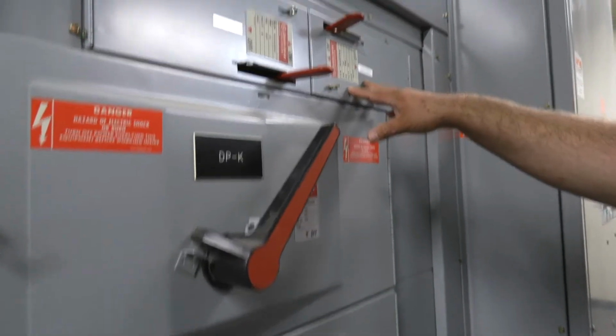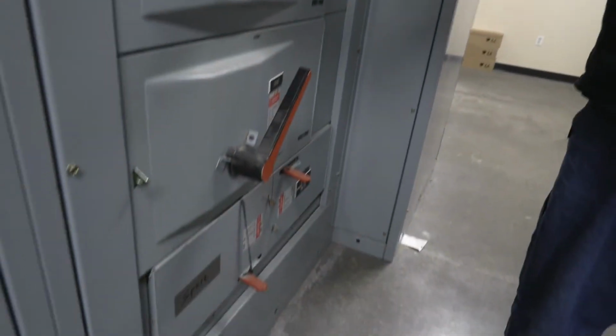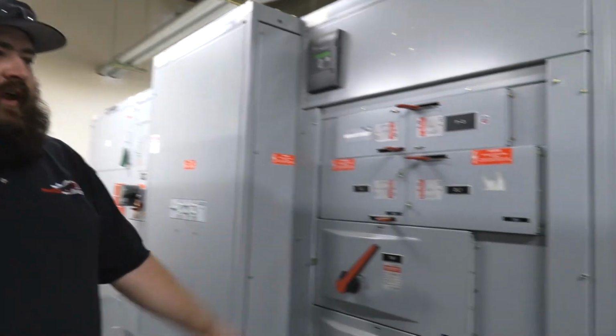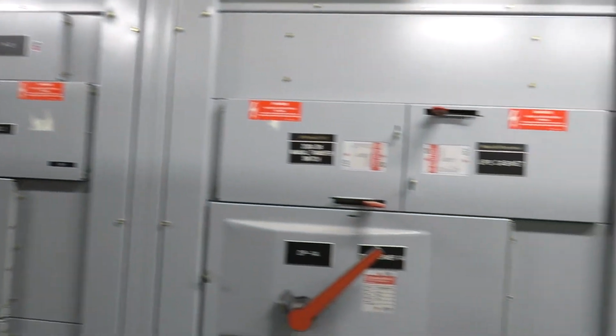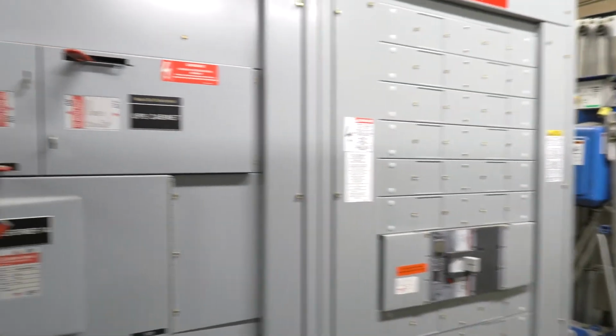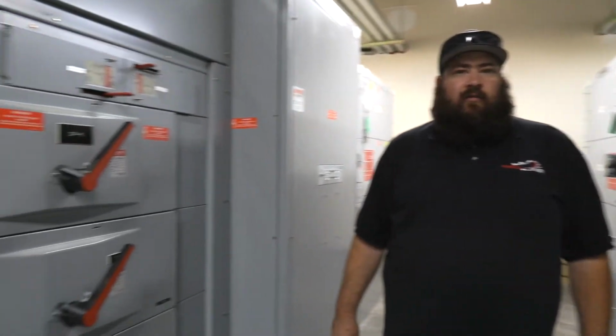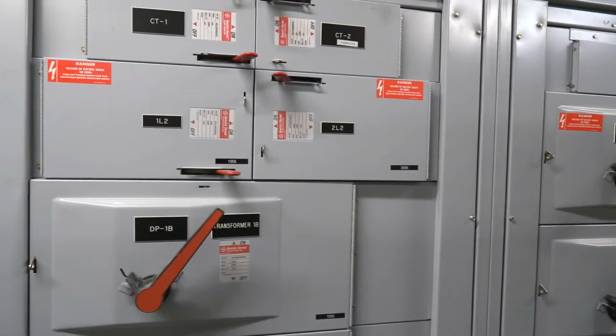And all of these are distributions to pumps for their AC unit, mechanical devices, transformers, panels. This is where you distribute to the rest of the building for power. We have them on both sides, and this is where we disseminate the first distribution to get to the rest of the building. Throughout the building, we'll have more distribution panels, more smaller panels. It just kind of goes down in series. Bigger distributes to smaller, smaller, smaller, until you're at a 20 amp breaker for an outlet.